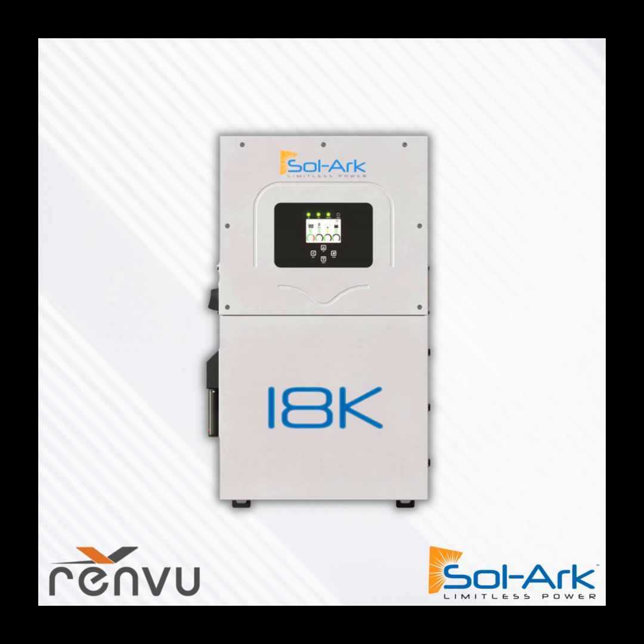If you have 400 amp service, you just add a second inverter. If you're really clever, you can get a 400 amp disconnect with a double lug, run to your 2 inverters, put in a power distribution block, and then run off to your 200 amp sub panels - it's that easy. You don't have to buy all this specialty combining equipment.